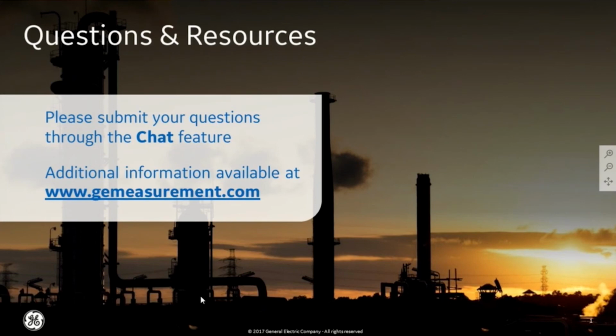Great. Then we have a question about reference reflectors. How can we get the instructions of reference reflectors while changing from one step to another in the calibration process? For example, while doing a velocity cal, take the SDH of 30 millimeter depth as the first reflector and the second is 60 millimeter. Can you get this on the screen while doing the calibration?